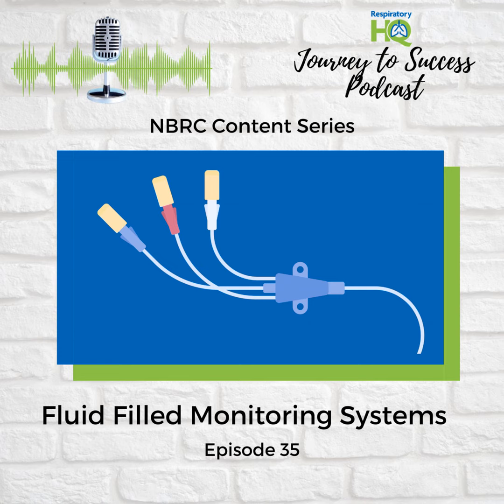Exactly. Now, damping is like if you lightly touch that vibrating string, it reduces the energy of the vibrations so they die out quicker. Right. And in our system, damping occurs because of friction in the tubing and the absorption of energy by the system's components. So too much damping would be like pressing down too hard on the string. It muffles the sound. That's a good analogy. And both underdamping and overdamping can distort the pressure waveform, leading to inaccurate readings.